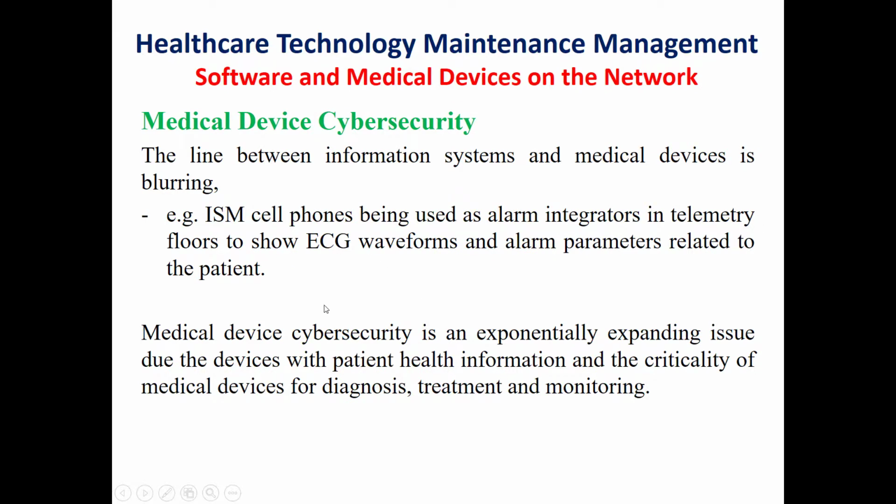A final point which is very important now is medical device cyber security, and this should be considered in the healthcare technology maintenance management program because medical device cyber security is an exponentially expanding issue due to the connection of the devices with the patient's health information and the criticality of medical devices for diagnosis, treatment, and monitoring.